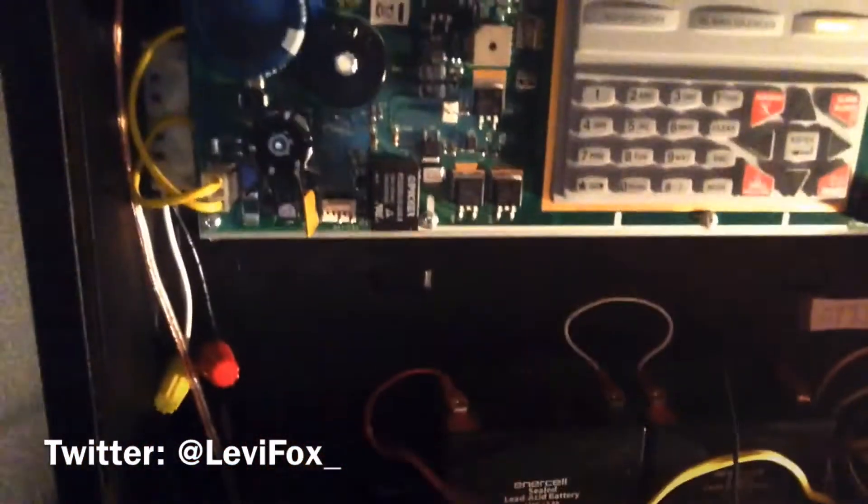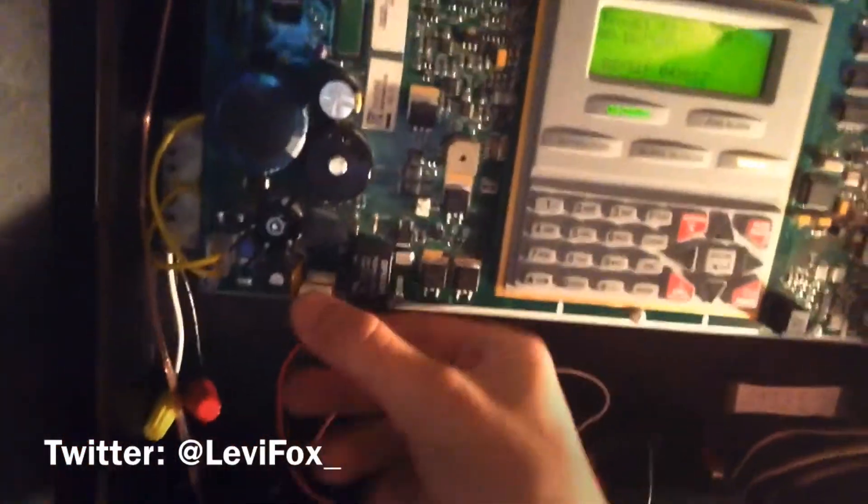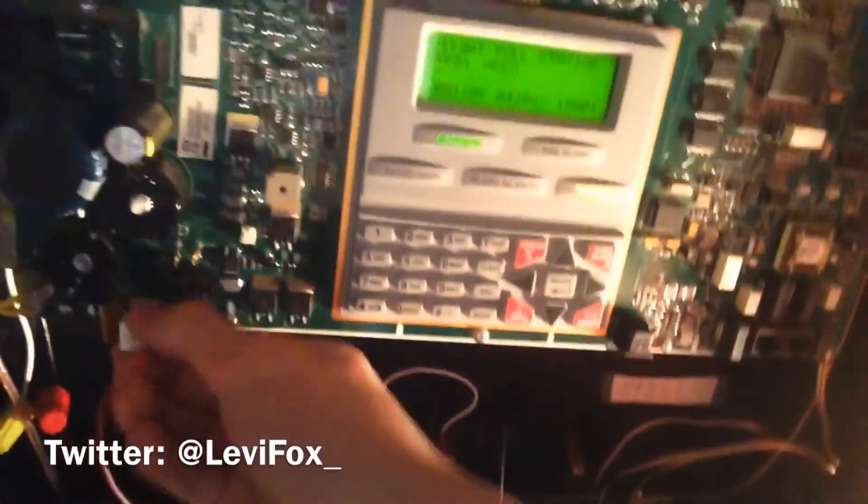What makes this panel different from other Fire-Lite panels regarding battery backup is that usually you just plug the battery cables in and out easily. But this panel has screw-terminal battery connections, so it's not easy to instantly disconnect the batteries. You essentially have to pull the terminals out to disconnect them, which can be a bit annoying, though I think it may actually be a better design. I always unplug the panel if I'm disconnecting the batteries.